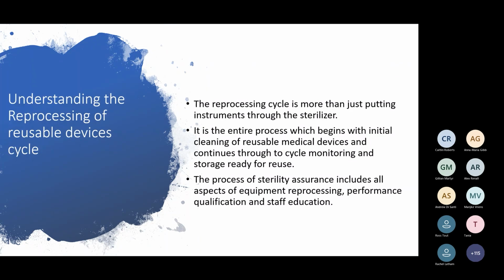The reprocessing cycle is more than just putting instruments through a sterilizer. It's the entire process, which begins with initial cleaning of your reusable medical devices and continues through to cycle monitoring and storage ready for reuse. The process of sterility assurance includes all aspects of equipment reprocessing, performance qualification, and staff education. So that's the whole process, right from point of use all the way through to back in a bag and stored on the shelf ready for reuse again.